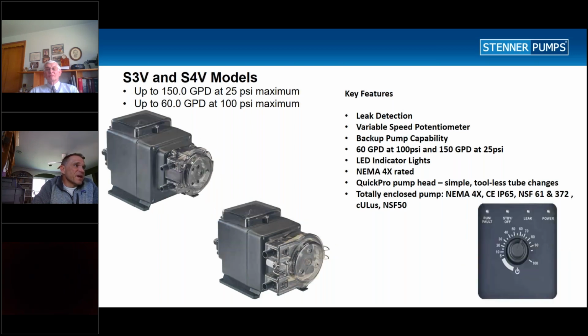Moving on from our fixed, we have our variable speed control. With this, you're still going to have the leak detect, the NEMA 4X enclosure, and the indicator lights here, which will show the run, fault, standby, leak detect, and power. But instead of having a feed rate control, everything is turned by a potentiometer dial. So on this, you can do all of your adjustments just by changing the dial. And the nice part about this pump is that when it comes to maintenance, there's no gear case and no feed rate control. All you have to worry about is just the tube, the rollers, and the housing.